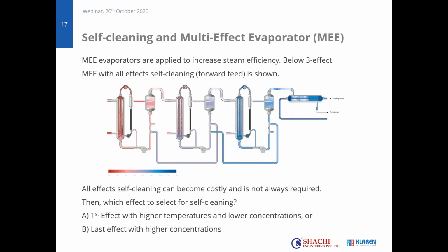So, self-cleaning and evaporation. Well, there are different ways in which you can use evaporation or convert evaporation into the design of an evaporator plant. You could go for the route of a multi-effect evaporator, or you could take the route of an MVR unit. And already upfront, depending on the customer situation, there are reasons to go for the ME route, and there can be reasons to go for the MVR route. In both cases, we can integrate our technology. Today, I will focus a bit more on the MVR. But some words first about the ME.